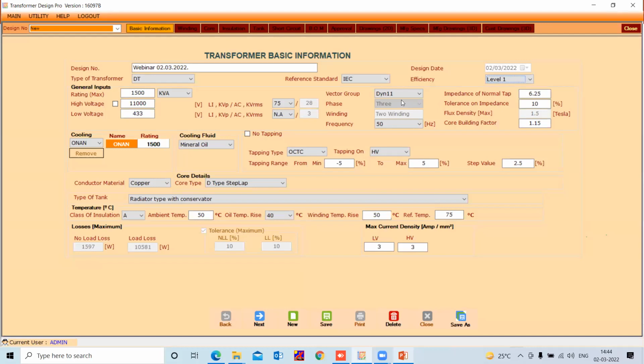You'll be in a position to set the losses whatever you wish to, but that will be possible as we go from this page to the next page, that is the winding page. Okay, let us select any level as you design now, and then let us go to the vector group. You may also have a question, what are these levels? As such, there is no significance of these efficiency levels. They are there only to indicate that the conventional is the highest losses and level 3 is the lowest losses, and level 1, level 2 are lower than the conventional losses. They are not relevant in terms of any standards, but you will be in a position to set them as you go on the winding card.